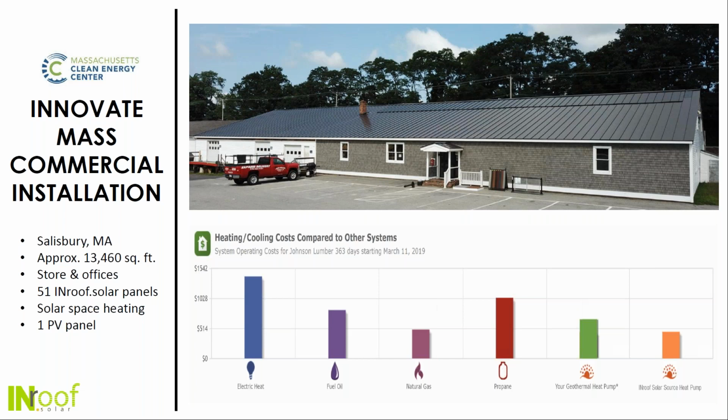So this was actually tied to a heat pump. And so we call it a solar source heat pump. We're taking energy from the sun, even in the middle of winter, we can do that very efficiently, putting it into some sort of storage. In this case, it's a relatively small storage tank. And then the heat pump operates its cold side. If you think of a geothermal heat pump, this is the side of the heat pump that would be down in the ground. And it then takes that energy, which is basically thermal energy, but at a relatively low temperature.